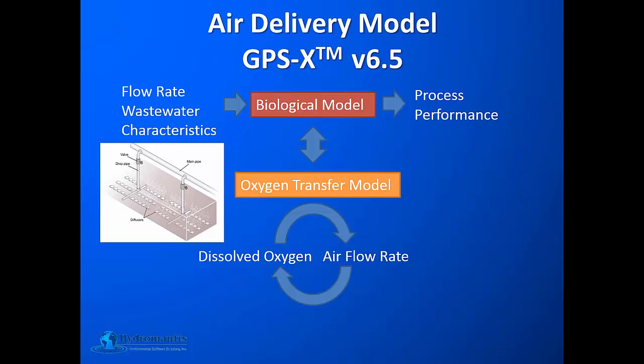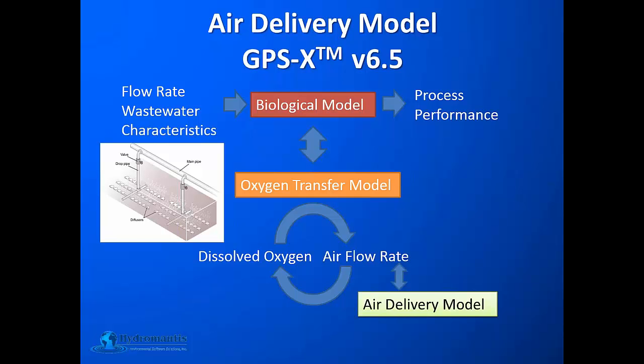Recently there has been interest in modeling the air delivery systems and the head losses that may take place in the diffusers, drop pipes, and distribution pipes, and to estimate what the blower pressure requirement is. To do that we need another model — an air delivery model — which can be used to estimate the head loss, the valve positions, the blower pressure, and the blower power in the system.